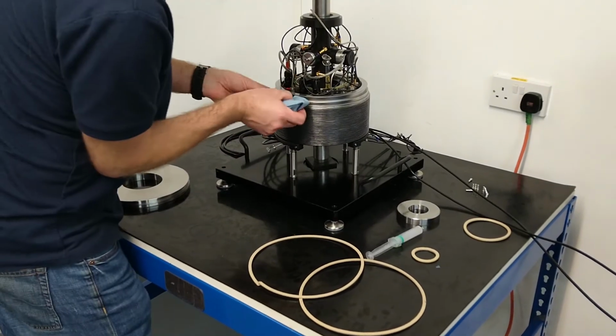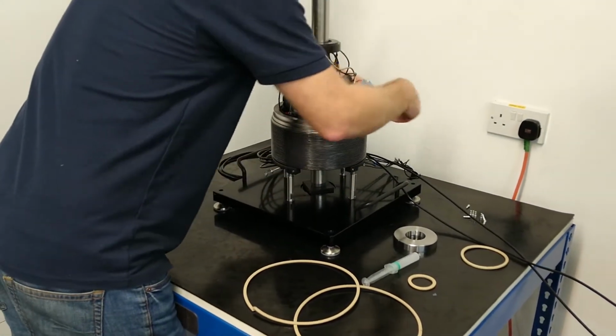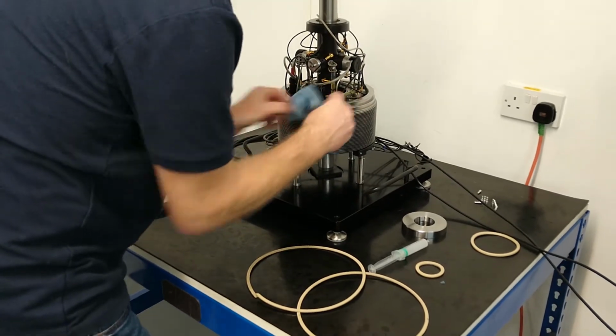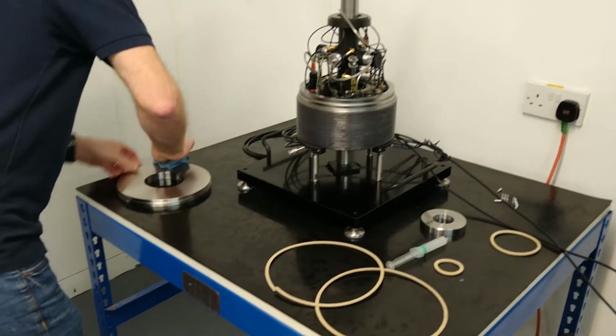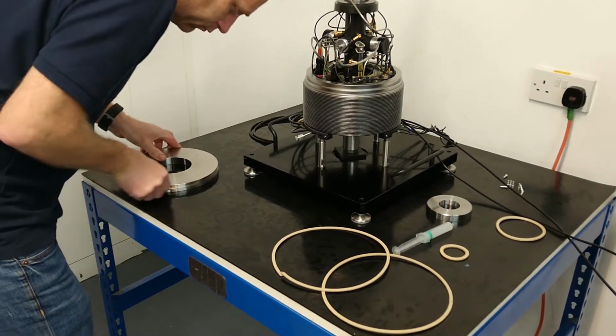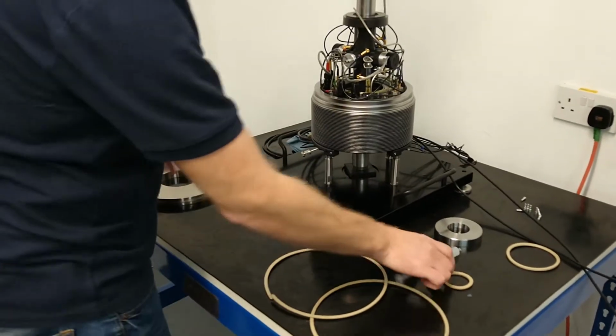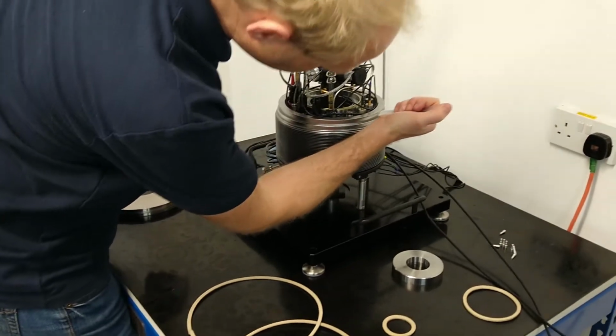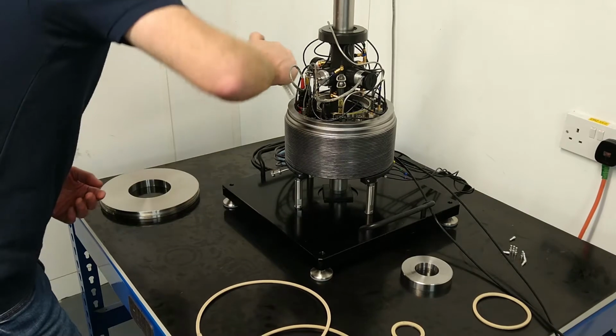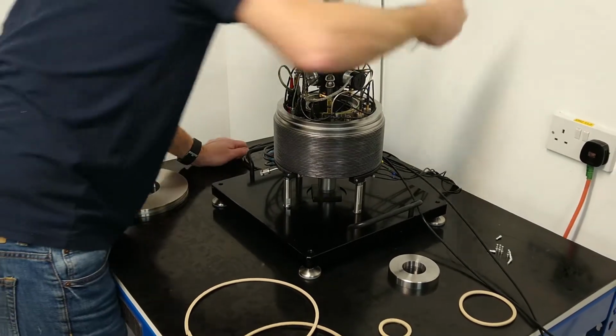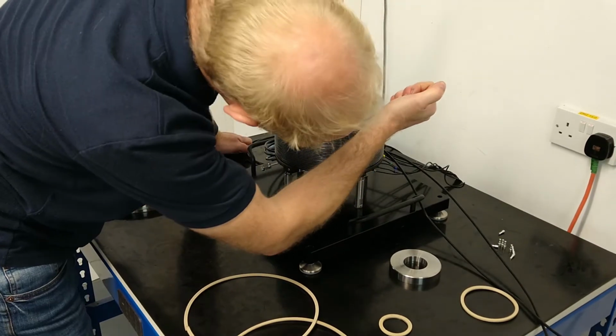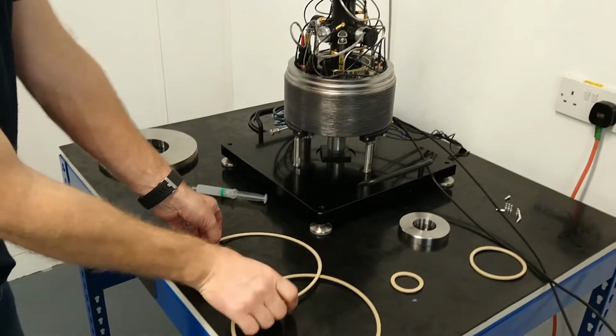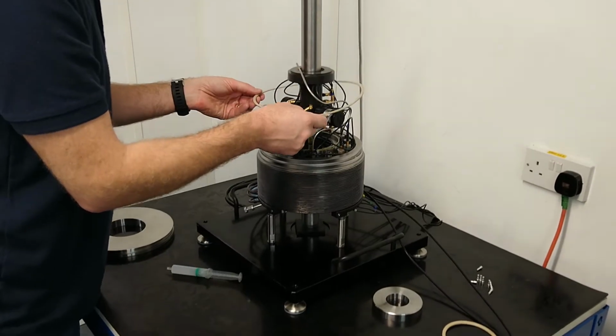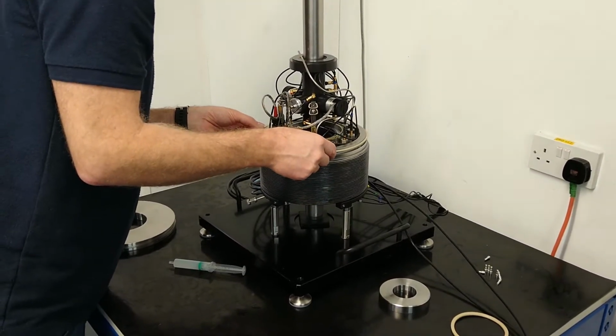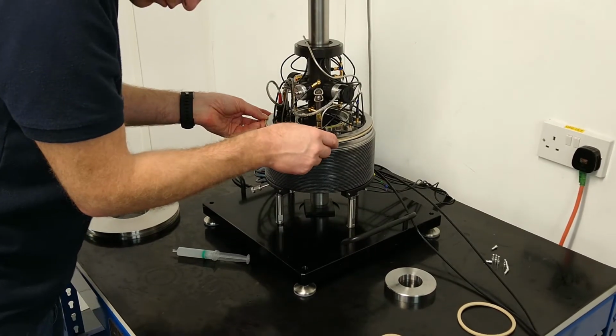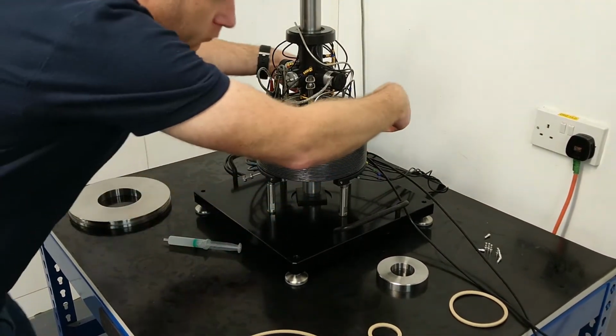Clean any residue and contaminants from the upper and lower sealing grooves. Apply a bead of silicone grease into the lower back corner of the cell base groove. Place the backing ring into the groove, taking care not to open up the ring too far, avoiding damage to its shape. Locate the join at the front, then push the seal down into the grease. Work from the back, around both sides, towards the join, ensuring the silicone holds the ring in place.